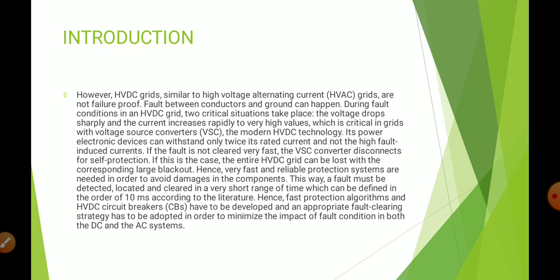During fault conditions in an HVDC grid, two critical situations take place. The voltage drops sharply and the current increases rapidly to very high values, which is critical in grids with voltage source converters. The modern HVDC technology's power electronic devices can withstand only twice their rated current and not the high fault-induced currents. If the fault is not cleared very fast, the VSC converter disconnects itself for self protection. In this case, the entire HVDC grid can be lost, with the corresponding large blackout.